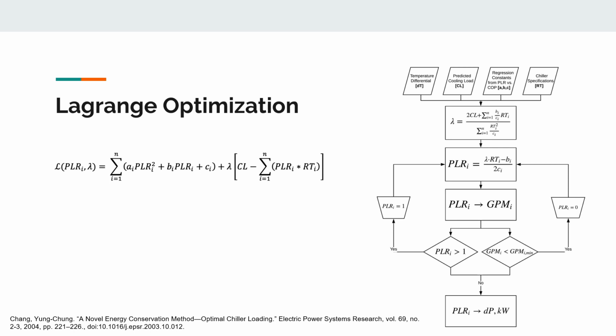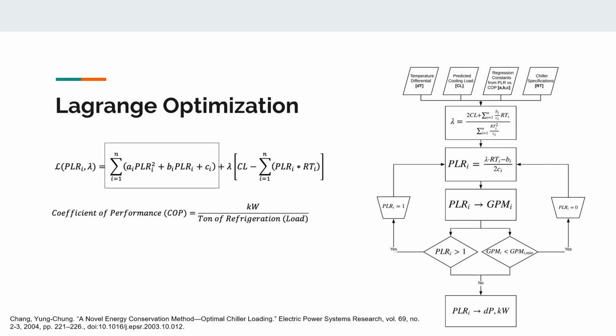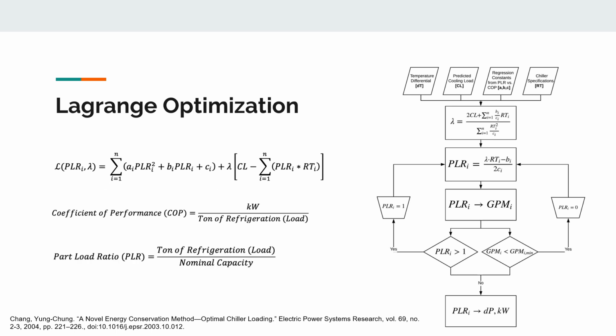For our system, the target function is the sum of individual chiller COP, the coefficient of performance, which is the required kilowatt of energy necessary to produce 1 ton of cooling, as a function of PLR, or part load ratio, essentially the operational power setting. This relationship was sought out since PLR versus COP shows characteristics while easily satisfying operational constraints and having obtainable regression constants using a second-degree polynomial.